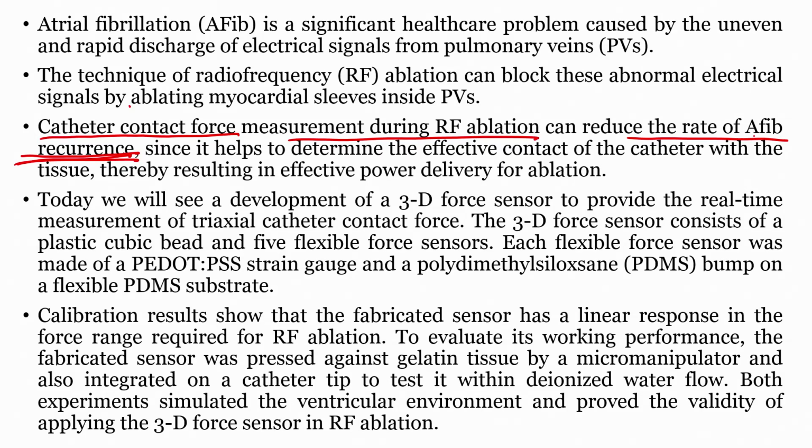So, how can it reduce the rate of AFib recurrence? It helps to determine the effective contact of the catheter with the tissue, thereby resulting in effective power delivery of ablation. So, catheter contact force is very important.